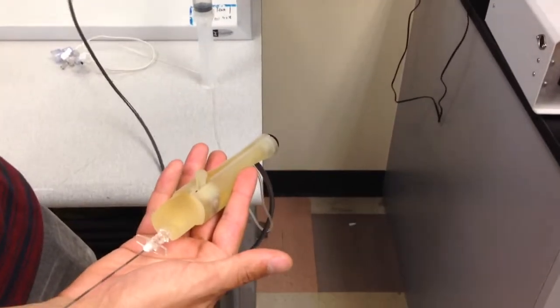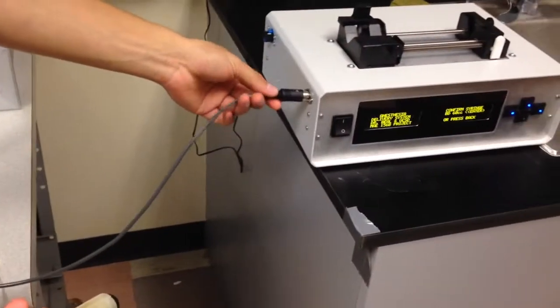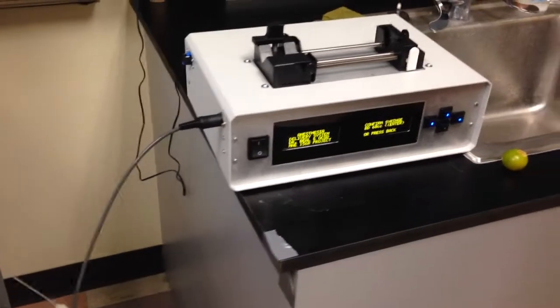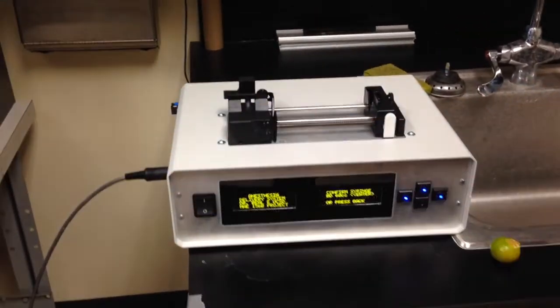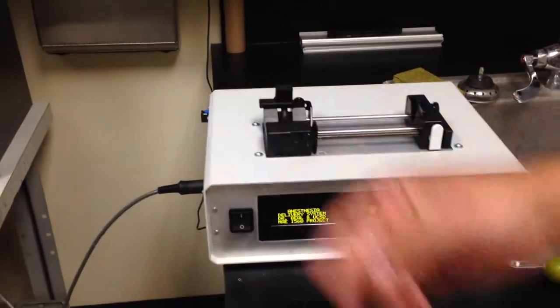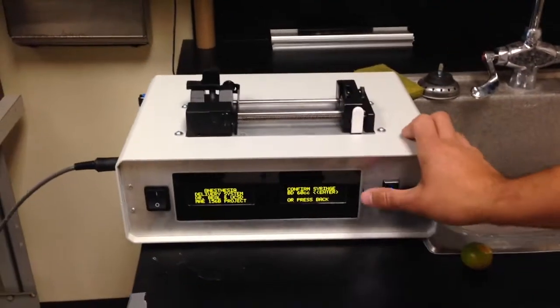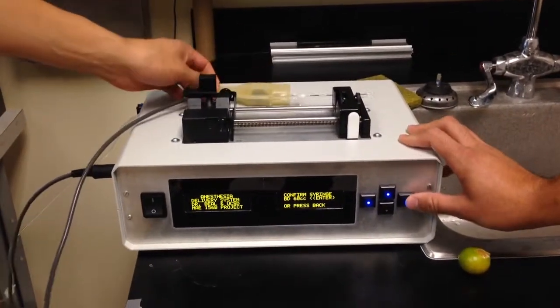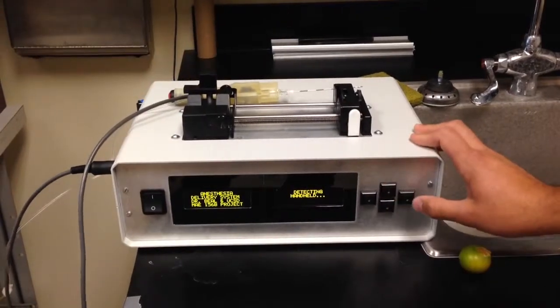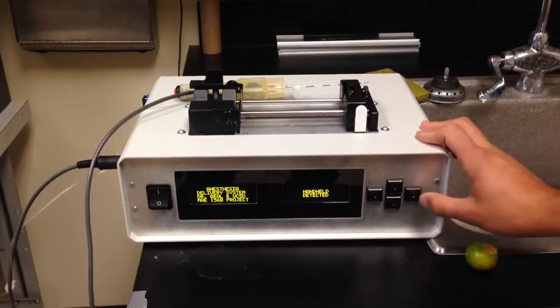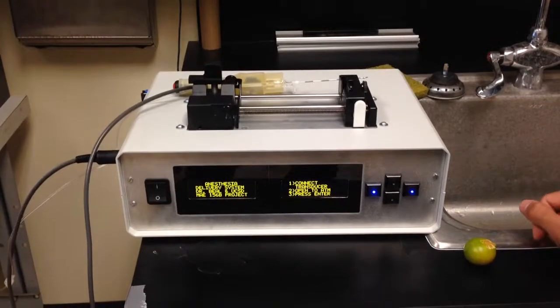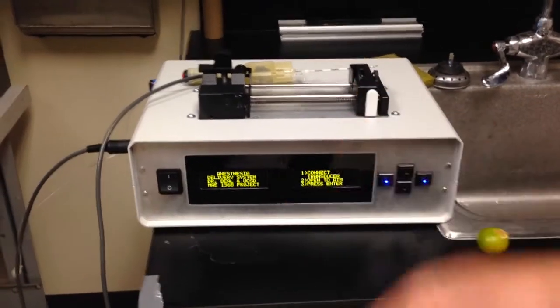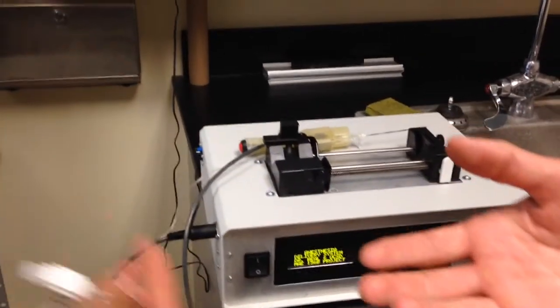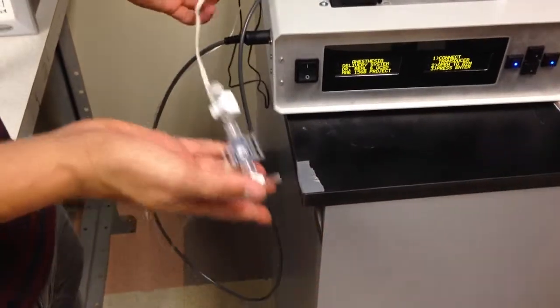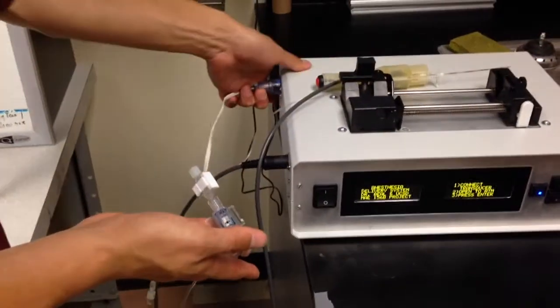Rene is holding the handheld device, which connects to our control box here. And the next thing would be the pressure transducer, which is there. So you confirm the syringe size, press enter once more, and this time when it detects the handheld, it will confirm that there is indeed something connected. The other step would be the pressure transducer. This is a disposable Transpac 4 medical transducer that connects to the side of our control box as well.